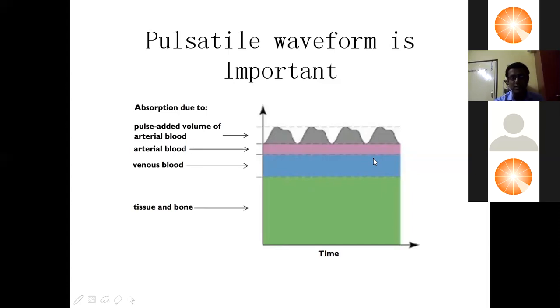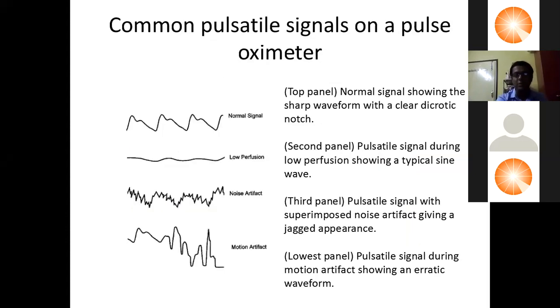If you consider this as a photoplethysmograph, this distance is absorbed by the pulsatile flow. This is called AC, and this distance is absorbed by the non-pulsatile flow. This is the systole and this is the diastole. The ratio of this AC and DC is called the perfusion index. So with the help of this perfusion index and the differential absorption of infrared and red light by the oxygenated and deoxygenated hemoglobin, we usually calculate this SpO2.